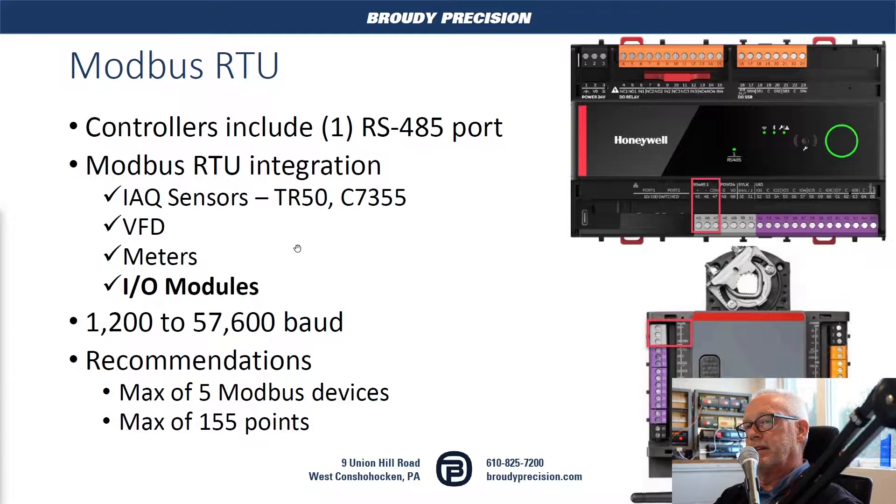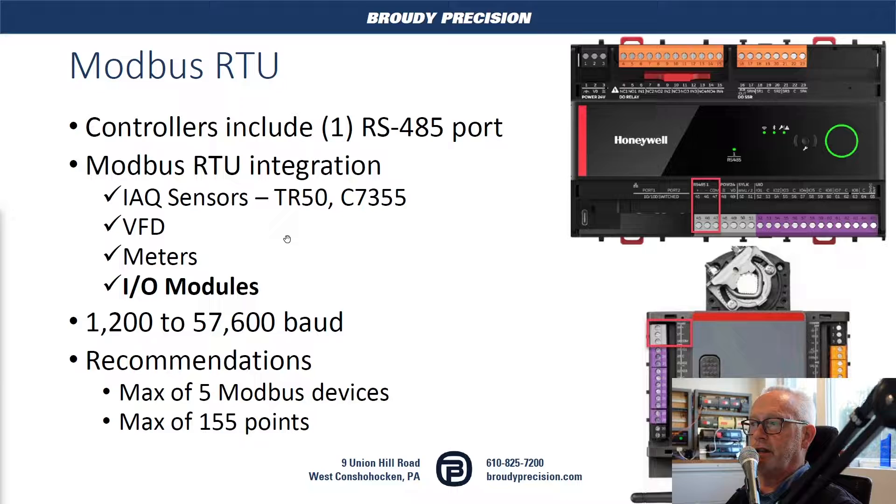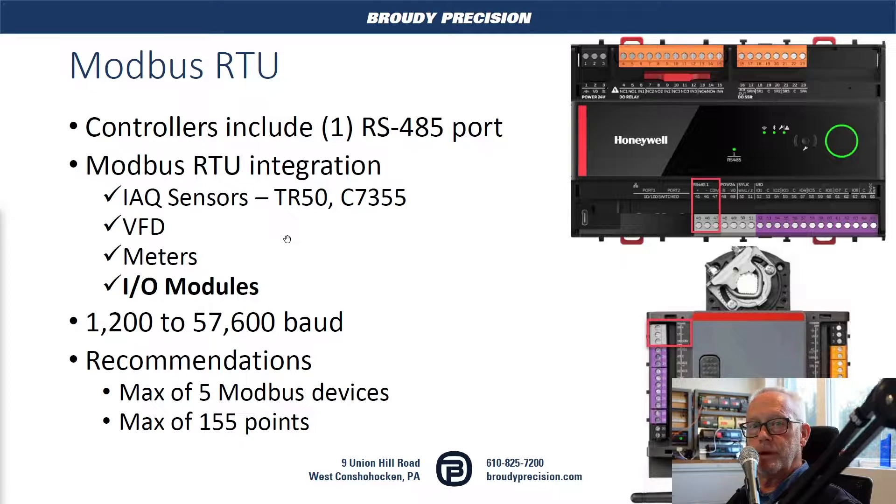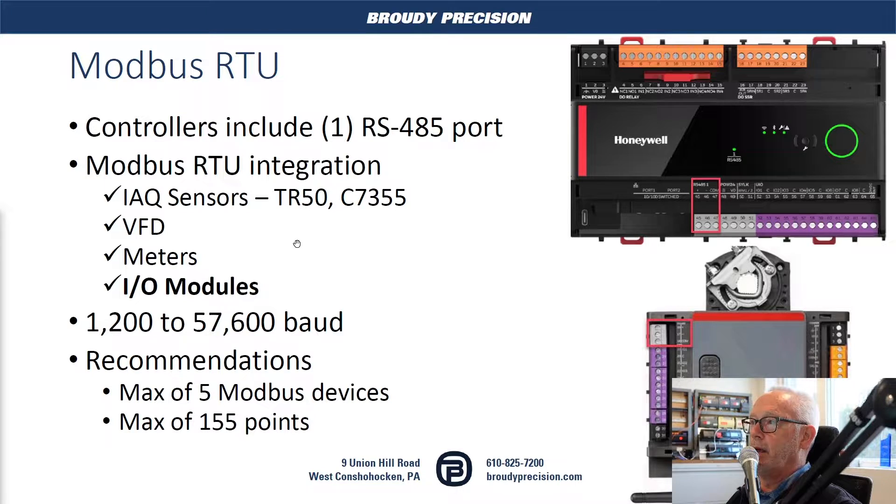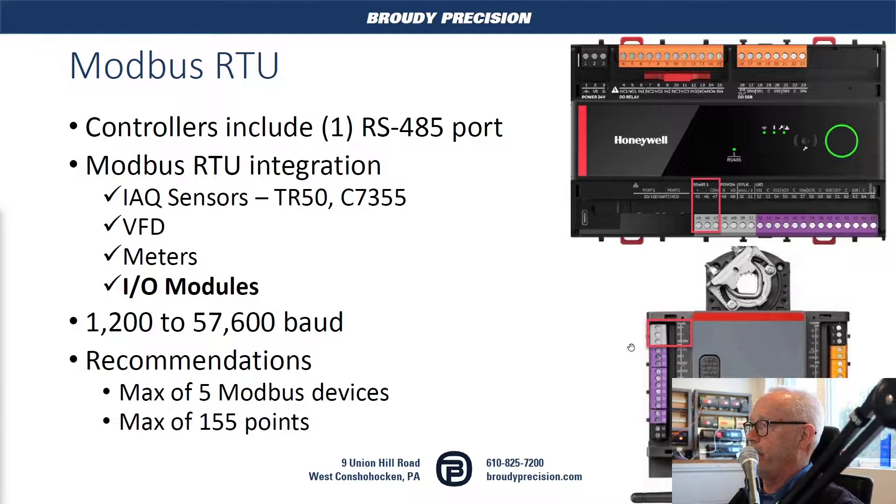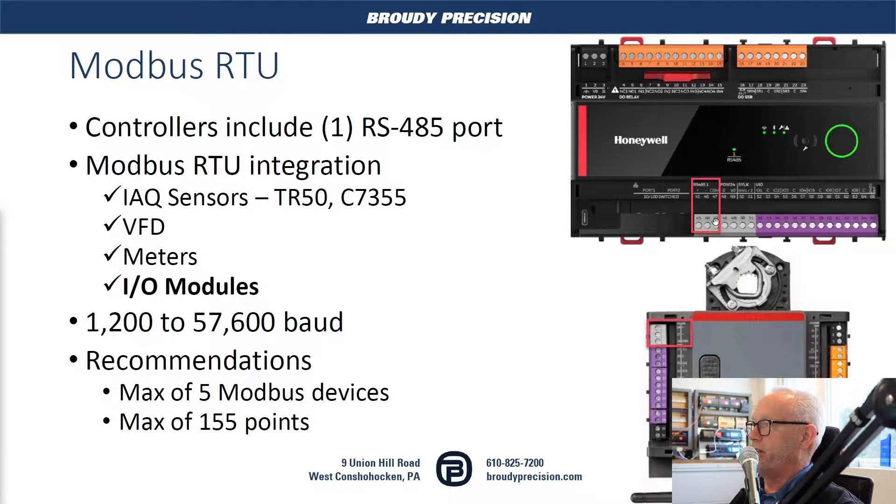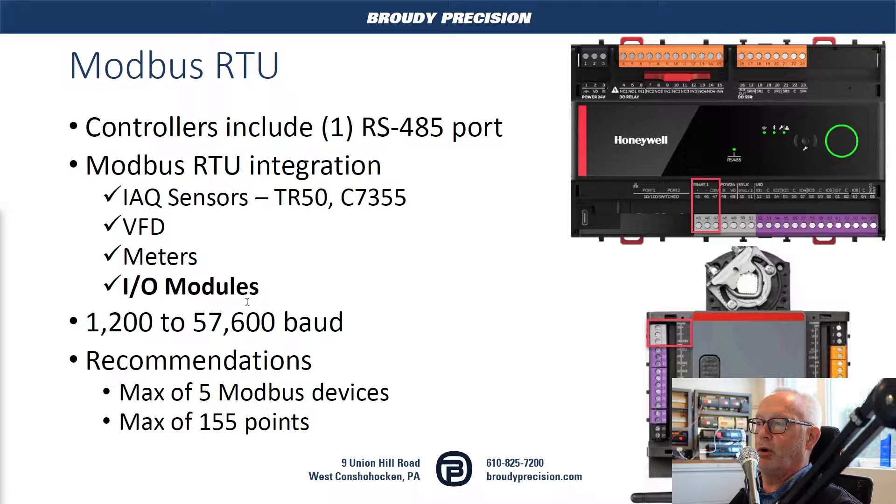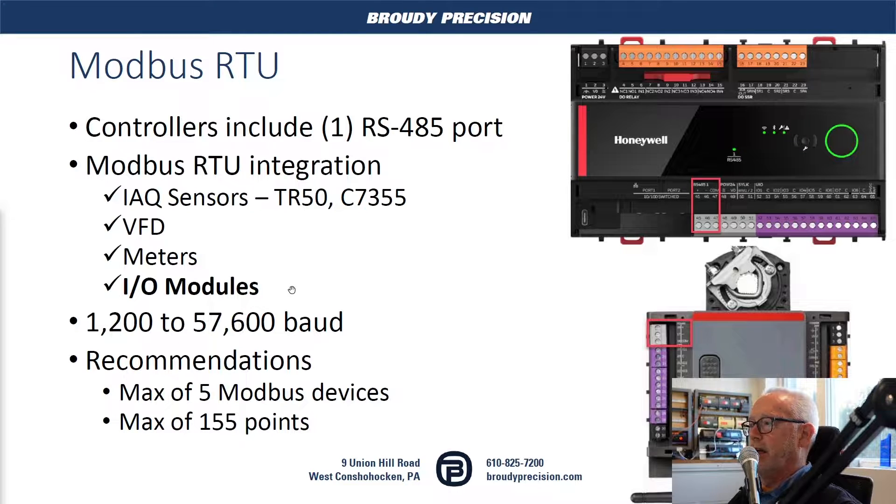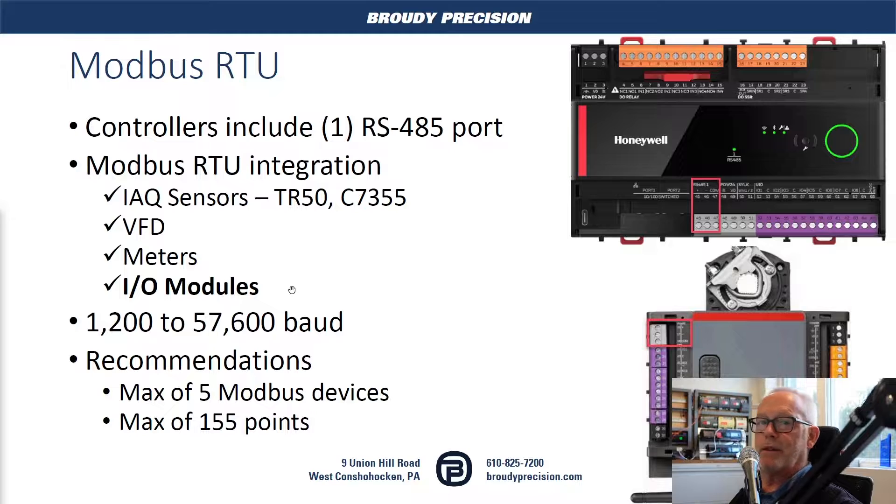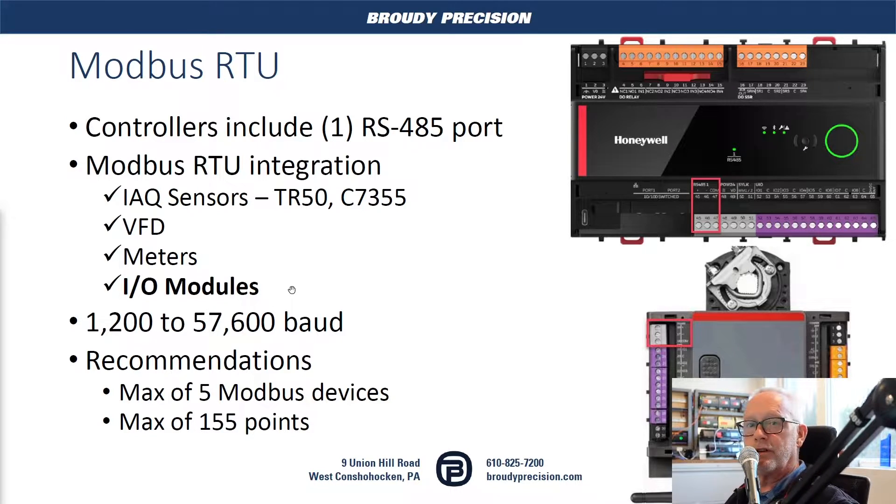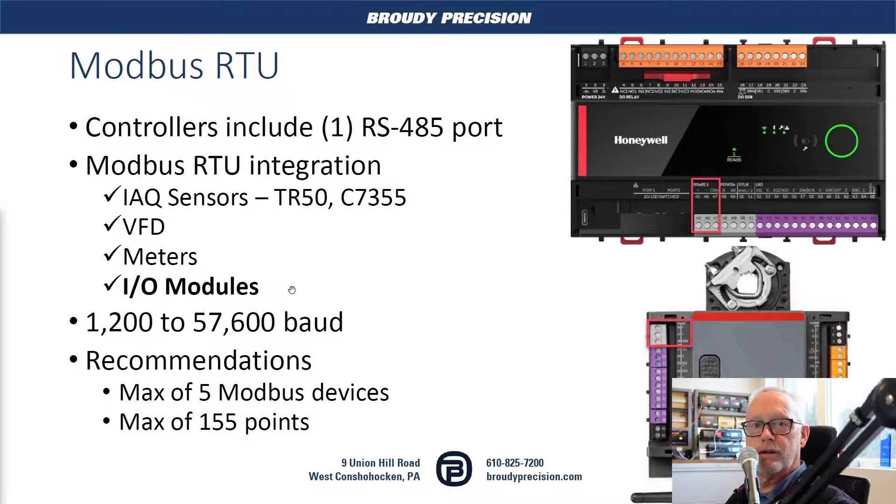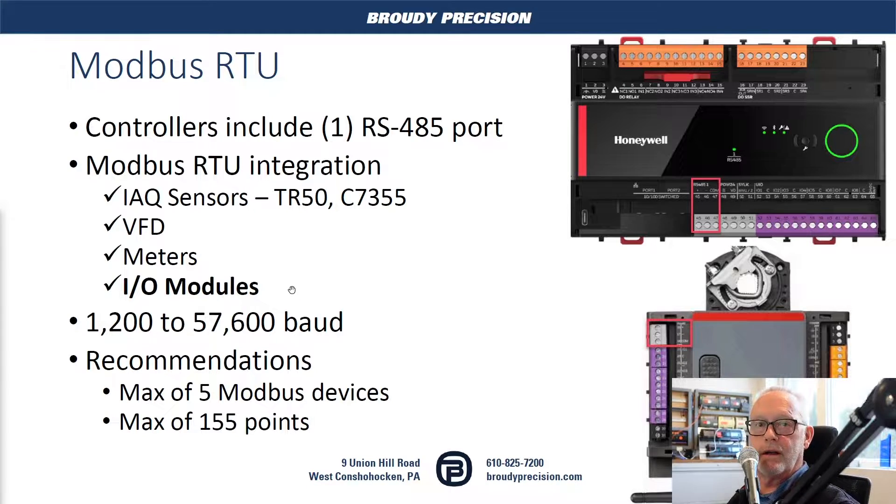The intent of this video is to discuss adding I/O modules to this controller so we can extend the I/O for bigger applications. Every unitary and VAV controller has this 485 port dedicated to Modbus RTU. The recommendations are to have a max of five devices on that bus and also 155 points. This isn't a hard fast number, but that is the recommended limitation for that port.